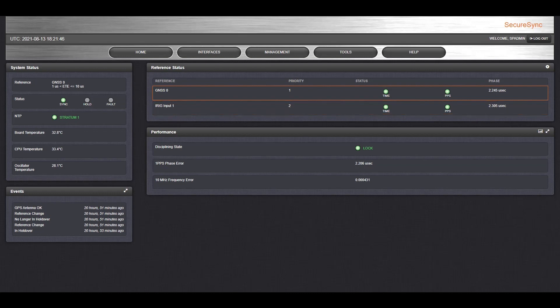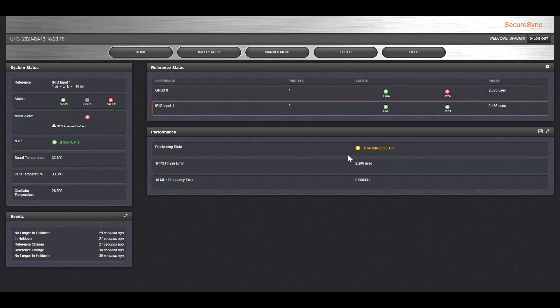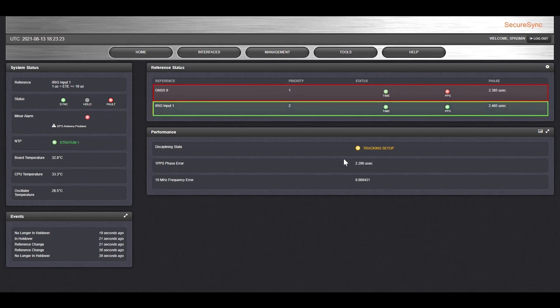If something happens, let's say your GPS antenna becomes disconnected, you'll see that status immediately in the performance window on the main page of the web UI. So let's take a look at what you would see if that were to happen. Now you can see immediately something has changed. My unit is still in sync, but there's a fault, and the web UI tells you there's a minor alarm and what the issue is. A GPS antenna problem, because I've taken it off for this demonstration. The time from the GPS is invalid, but the time from the IRIG input, our backup unit, is still valid because it automatically switched to the next reference source.